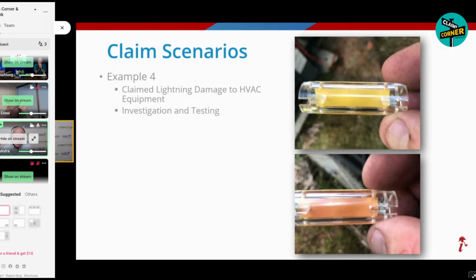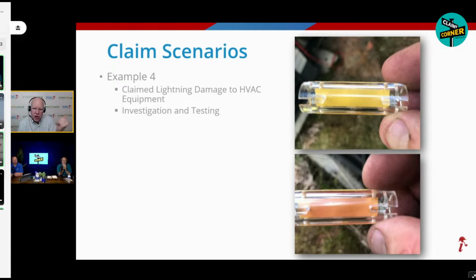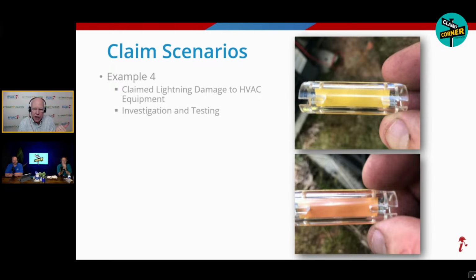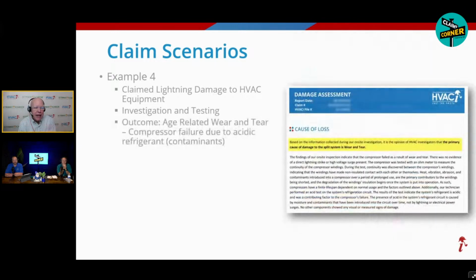If it changes even a little bit, it's got acid in the refrigerant. Acid in the refrigerant is not sudden and accidental. Acid in the refrigerant will cause the compressor to stop working over time. So our report on this one says: wear and tear related compressor failure due to acidic refrigerant from contaminants. Might have been from a refrigerant leak, might have been from a bad technician working and mixing refrigerants, things like that. So this just goes to show you how many times this does happen.